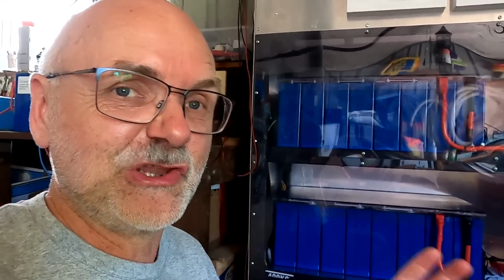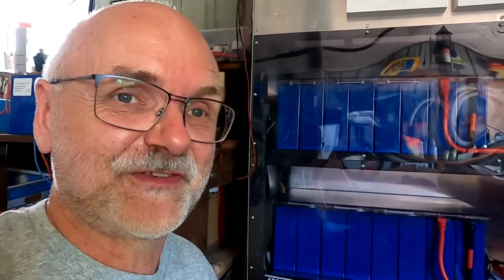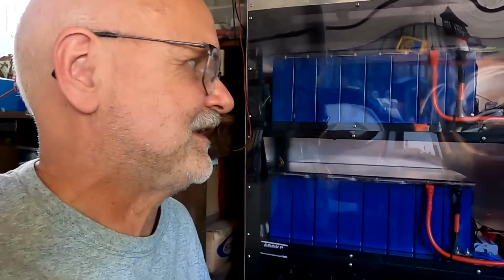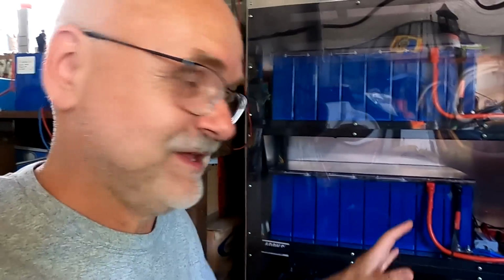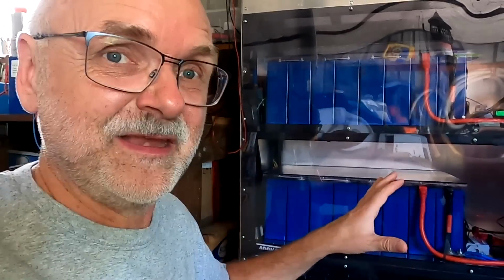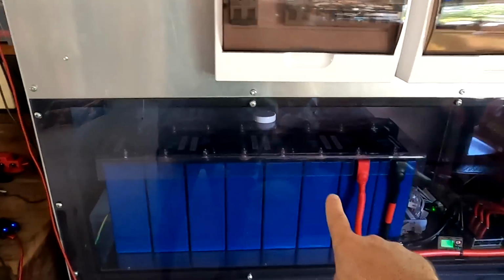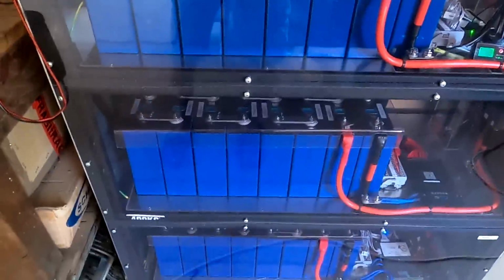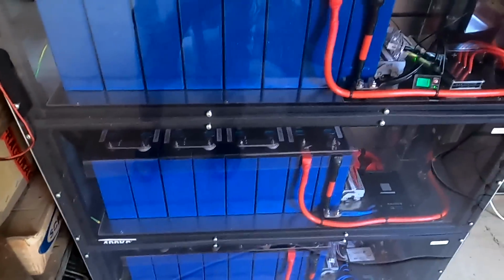This is 5 kilowatts of charging or discharging for the battery. I'm not having a huge load on the system here, or I charge in full sunshine as I do right now. But this afternoon, just for the sake of testing, I wanted to measure the full power here going through these battery banks and see if there are any major issues. So top battery is fine, this one needs some attention, and the bottom battery is fine as well.